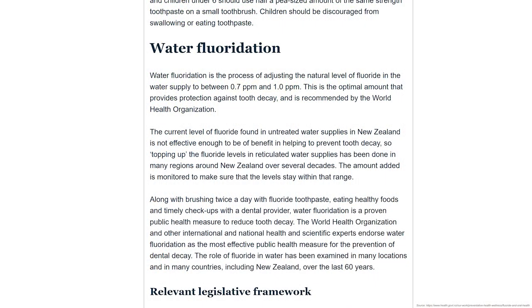Okay, so obviously you said when it's diluted to the right dilution it's fine, it's safe and it's healthy. So I guess there's a lot of controls in place at plants to enable that? Yes, that's correct. Within New Zealand the current Taumata Arowai guidelines and the old drinking water standards set a maximum limit on the concentration of fluoride which is 1.5 milligrams per liter. That's considered the maximum allowable value. So that's what's considered a bad dose. A typical dose is in the range of 0.7 to 1, which is what the World Health Organization recommends for dental health protection.